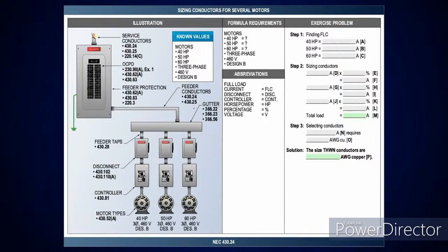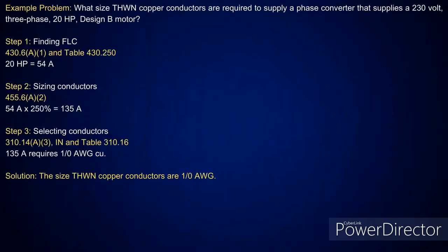Okay? So is there any case where you would have to apply, like if you were under 100 amps, you would have to apply 110.14(C)(1) for that? Well, the terminals are unknown, you want to go to C1B, it gets into the motors, and that's where you got the 75 degree C. But you got to be careful because if it's an older motor, it could be 60 degree C termination, and then you would be using the 60 degree C column.